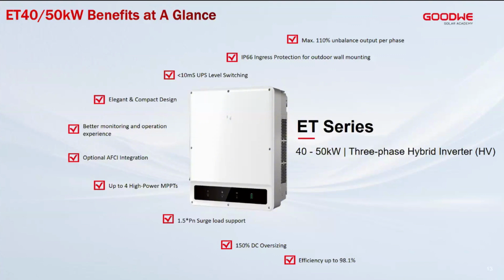Now, with the DC oversizing, just to cancel out the losses on the PV side, or even reduce the duration you would like to charge your batteries, the ET50 can oversize the DC or PV capacity up to 150%. That's a unique feature. If you couple that with the high MPPT rating, then you'll be increasing your self-consumption or even working better in the off-grid connection mode. The efficiency of the inverter is also high, reaching up to 98.1%. These are the points that make the ET series a hot topic and the best hybrid product for your C&I market.